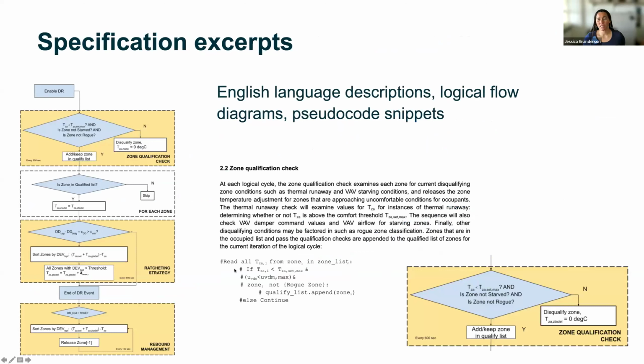When I say open spec, I wanted to give an example of what we really mean by that. So we have logical flow diagrams. On the left, I show the whole chain for zone temperature-based adjustment to do a demand shed. We have an English language description, so I pulled out a little excerpt there for the zone qualification check. A little bit of pseudocode snippets go along with it to further convey what we mean by the diagram and what we mean by the English language.